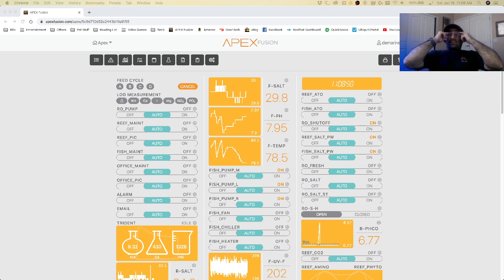Yeah, I think that's right. Flip the side of the optical. I think that's great. If you just switch them around like Devin said there, I think that's the right thing to do. The problem is they get hit with water and then it just dries up and then you get salt creep and then the optical sensors stop working.